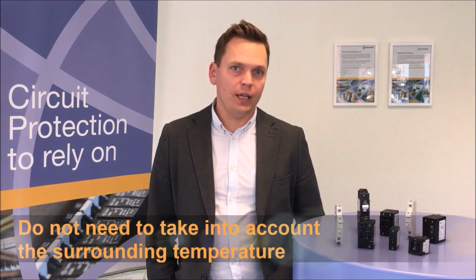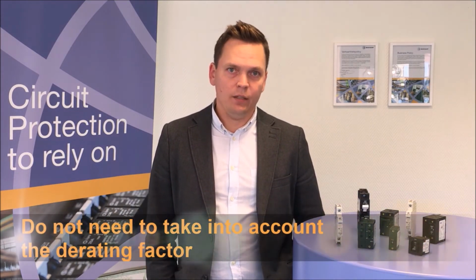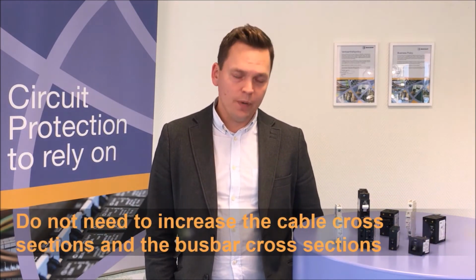What is the implication of that then? Well, it could mean that in an application you would need to upsize the thought out 32 amp breaker to a 40 amp breaker. In turn, you would also need to increase the cable cross sections you need to connect or the bus bars you need to connect. That creates cost. Choosing a CBI hydraulic magnetic circuit breaker instead of a thermal circuit breaker would mean that you do not need to take into account the surrounding temperature, meaning you do not need to take into account the derating factor, meaning that you do not need to size up, which then in turn means that you do not need to increase the cable cross sections or the bus bar cross sections, and at the end of the day that will save cost. Now, let's have a look at the Q-frame.